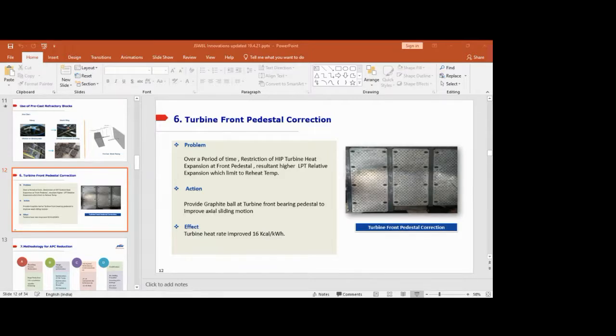So the action was taken. Where the HIP pedestal is sliding, we provided graphite foil, because graphite foil provides good axial sliding motion. By doing this modification, our axial movement was achieved again and the relative expansion reduced, and we are able to maintain the reheater temperature again. The turbine heat rate improved by 16 kcal per kWh.